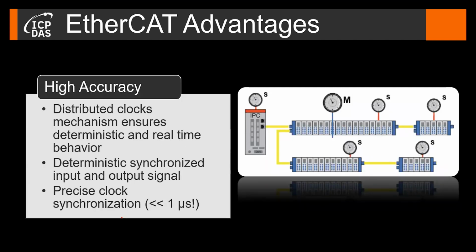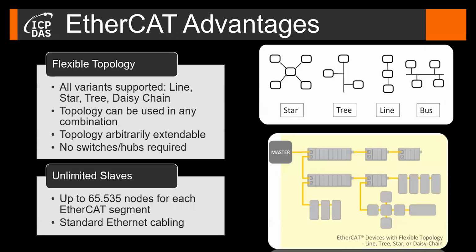EtherCAT slaves use the distributed clock mechanism to ensure deterministic and synchronized behavior of all the slaves in the network. Each slave is equipped with a separate clock, which is precisely synchronized across the EtherCAT network. The distributed clock mechanism ensures that all slaves read input data and write output data synchronously. This ensures that all the input data, such as digital signals, sensor values, and motor position measurements, are captured at the same time. In addition, all the output data, such as actuator values and commanded motor position values, are output synchronously. So exact synchronization is particularly important for precise machine control. For example, this is the case for applications in which multiple servos execute coordinated motion movements.